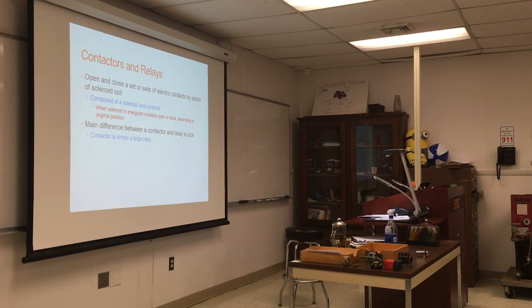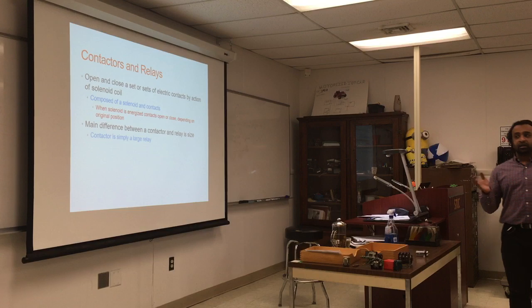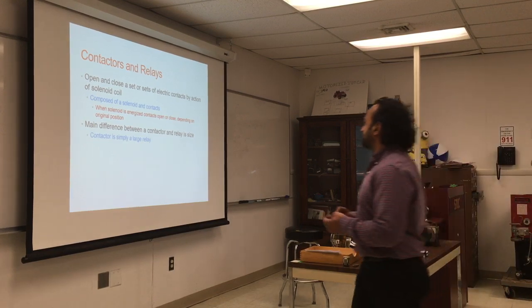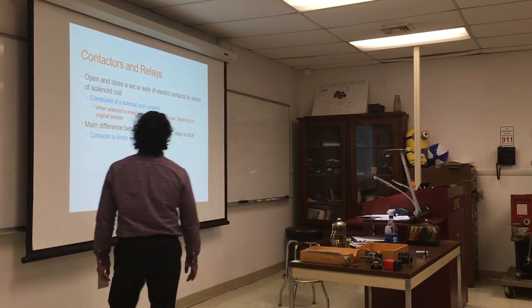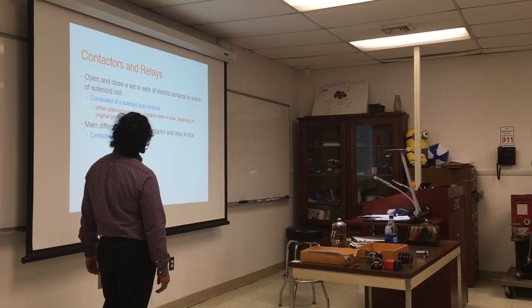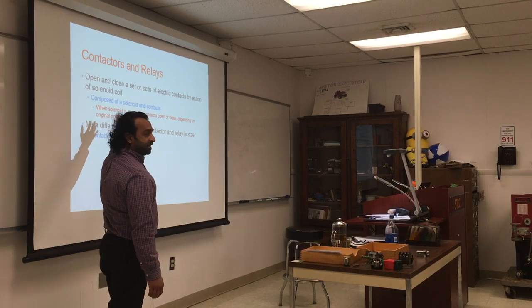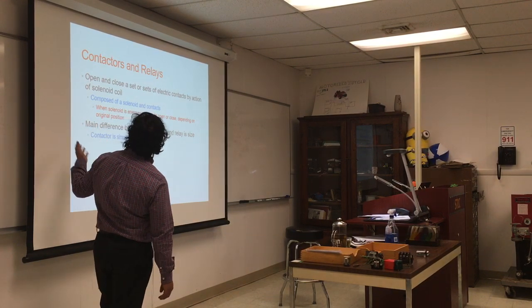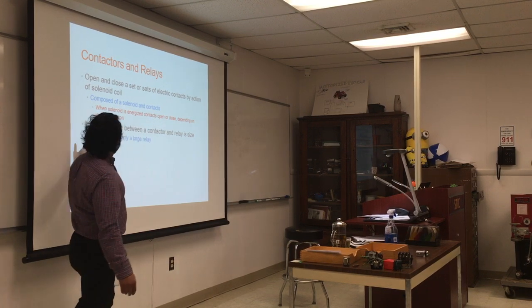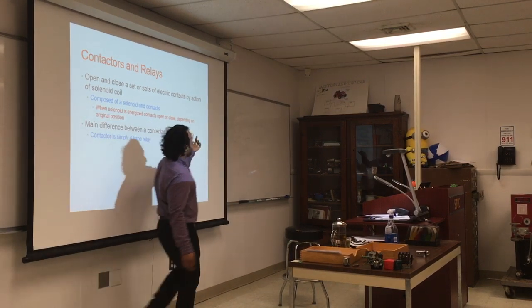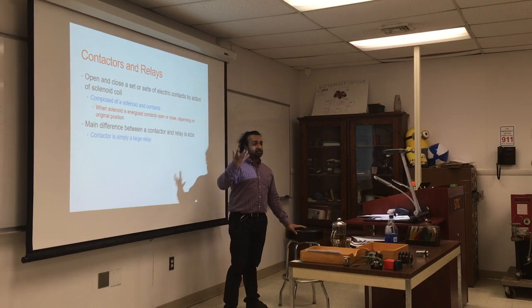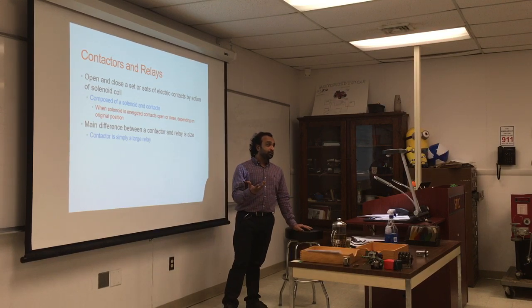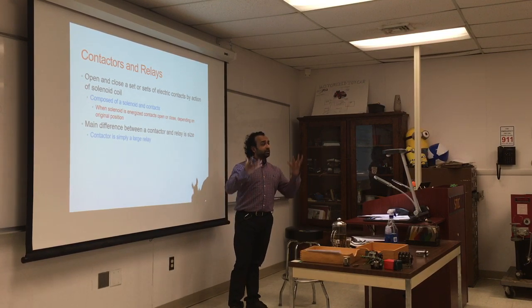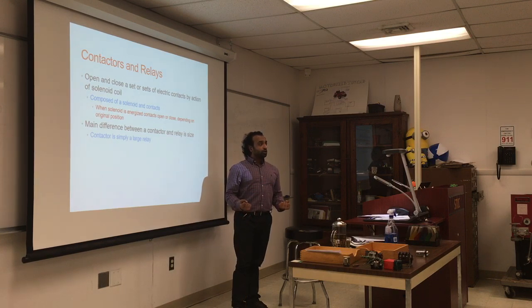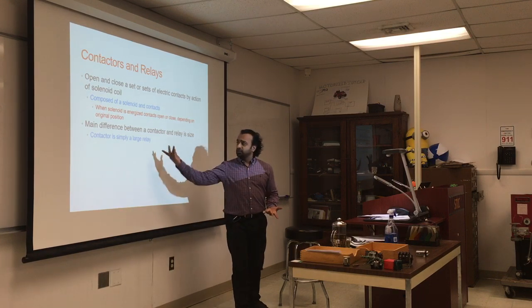And that's a contactor. If you remember that, a contactor is a relay that's more than 20 amps. You can just forget the rest of the class. It doesn't matter. When the solenoid is energized, it closes a set of contacts. The main difference is the size, not the physical size, but the size of the amperage that goes through it. It has a bigger magnet, has to pull strongly on two sets of contacts, and is simply a large relay.